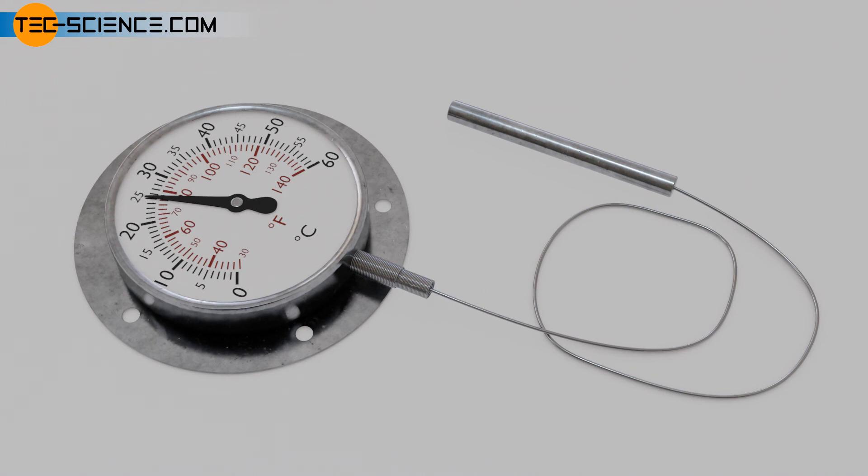If very large heights are to be covered with a capillary tube however, a pressure gradient due to the hydrostatic pressure may have to be considered, which falsifies the measurement result.